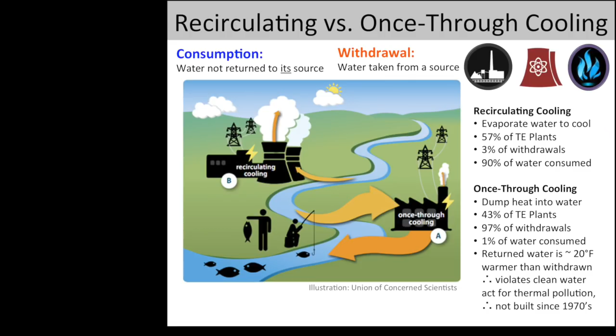There are two types of cooling at thermoelectric plants, in addition to dry cooling: recirculating, and once-through or open cooling. In recirculating cooling, you have a recirculating loop, but you have to cool that condenser with a cooling tower that basically uses evaporation. So while it's 3% of the withdrawals, it's 90% of the water consumption, because virtually all the water running into that cooling tower is evaporated.